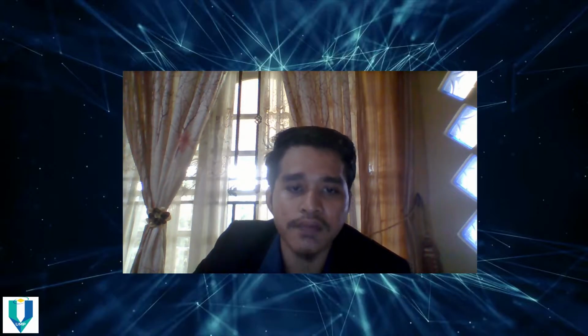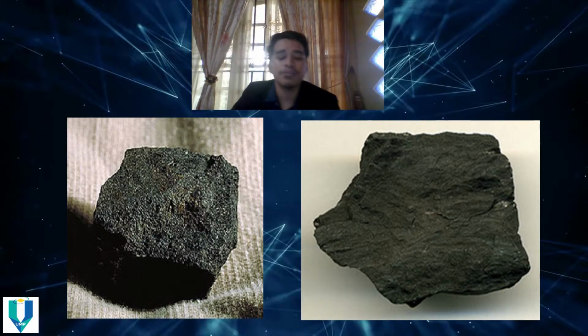The plant can burn either bituminous or subbituminous coal with a calorific value ranging from 5,000 kcal per kilogram to 6,600 kcal per kilogram, moisture content of 9% to 35%, sulfur content of 0.1% to 0.94%, ash content of 1.5% to 13.9%, and fixed carbon content of 35% to 54%. On the left side is an example of bituminous coal, and on the right side is an example of subbituminous coal that has been used in Sultan Azlan Shah Power Plant.